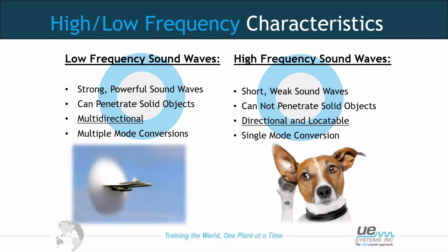When we get to high frequency sounds, the wavelength of the sine wave of the sound becomes shorter and it's weaker, which means that it's more directional from its source, and it cannot penetrate solid objects. It will become trapped within the object and will not pass through. So this will help us with identifying the source of the sound if we're using an ultrasonic device. As we point towards the source of the sound, we will hear it stronger. As we move away from the sound, we will lose it. So it helps us with pinpointing where it's coming from.